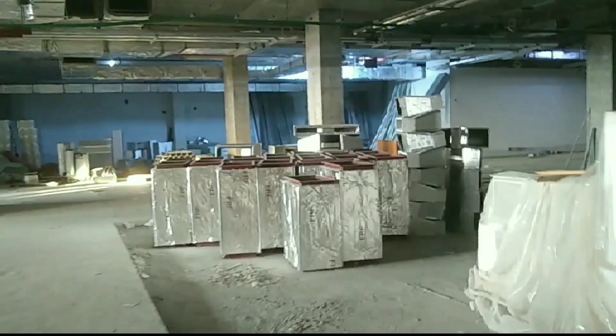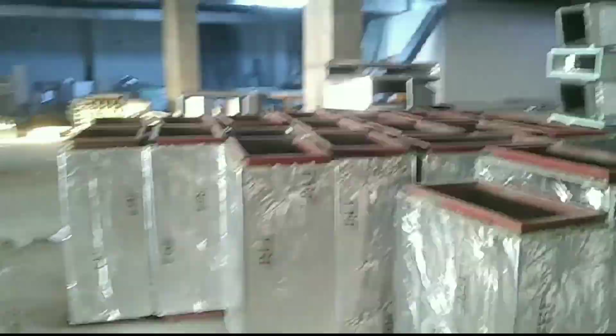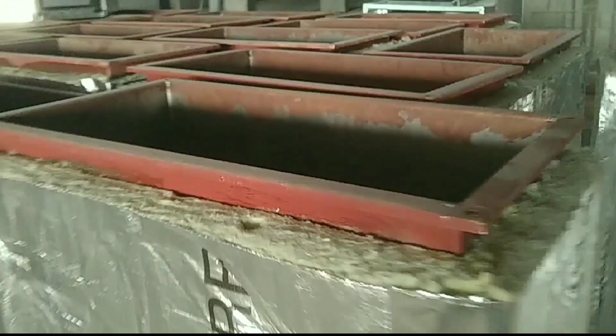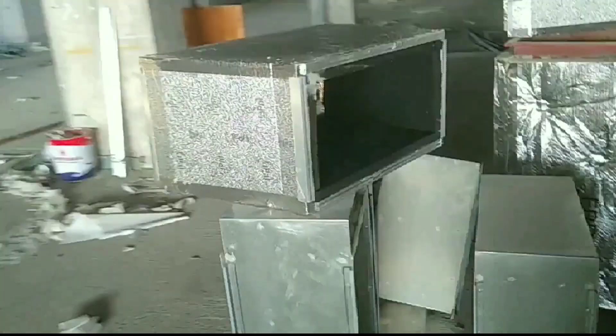Now you can see this work area with the kitchen extract ducts, which are carbon steel ducts. You can see here the insulation, with a thickness of 50mm - we use rock wool with 50mm insulation on the carbon steel duct for the kitchen extract duct. For fixing this rock wool insulation, we use sticker pins and normal GI glue as adhesive.